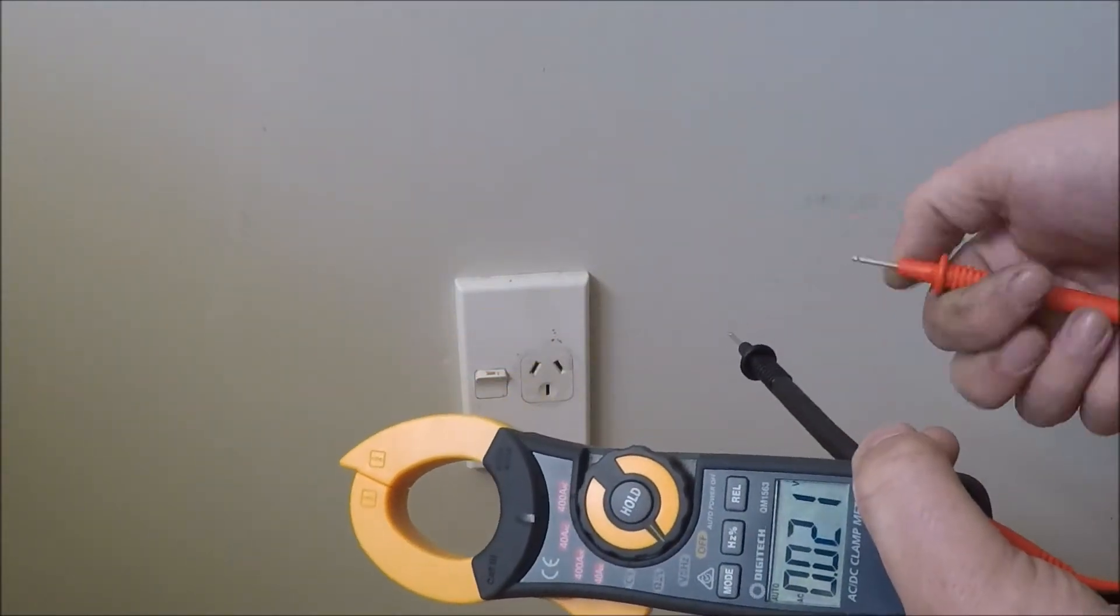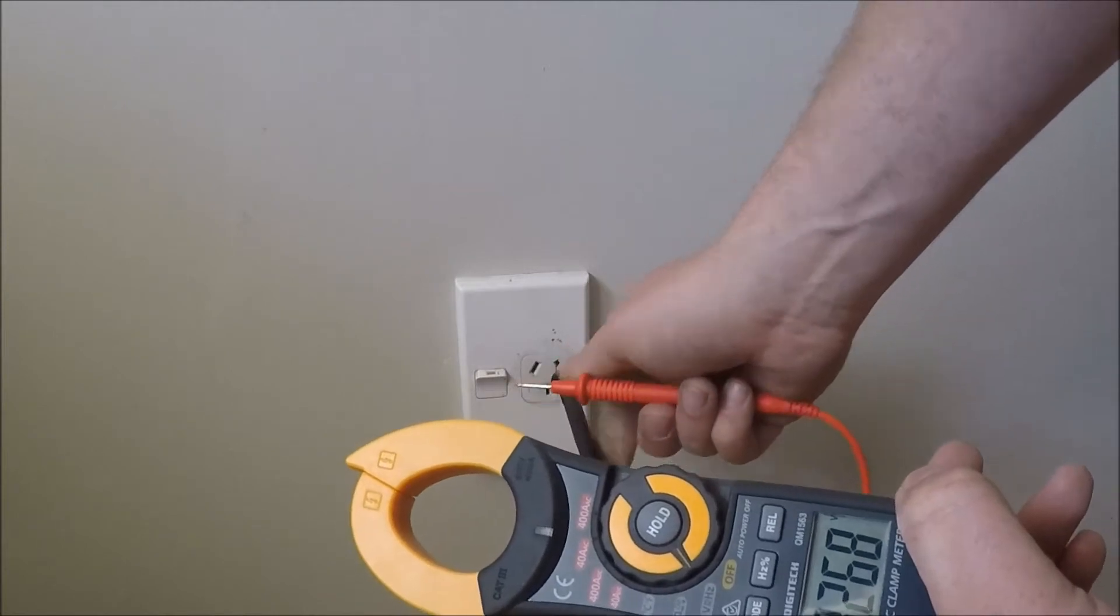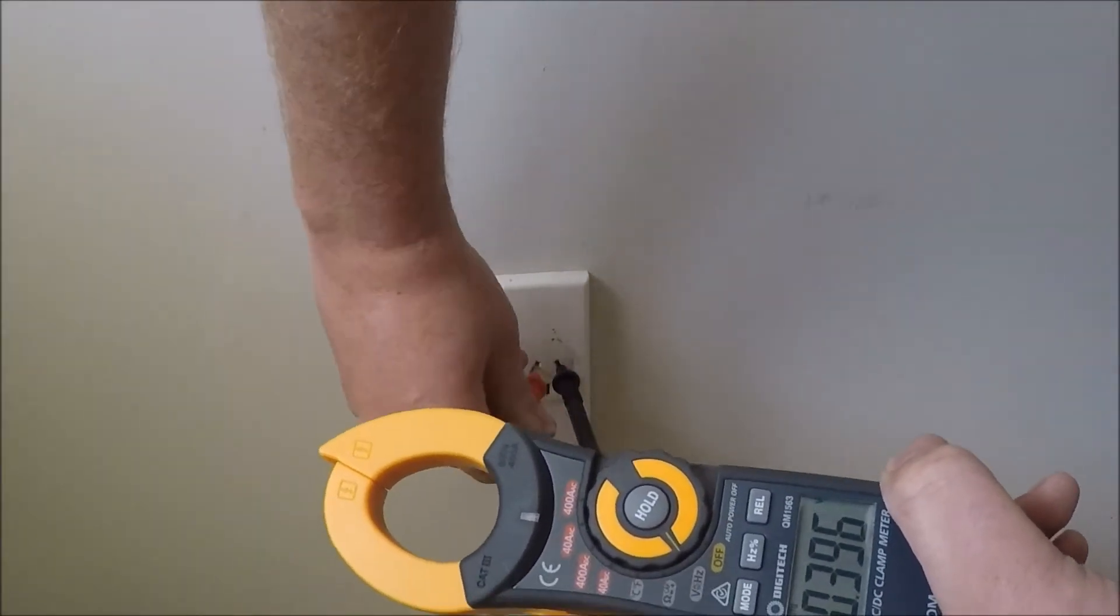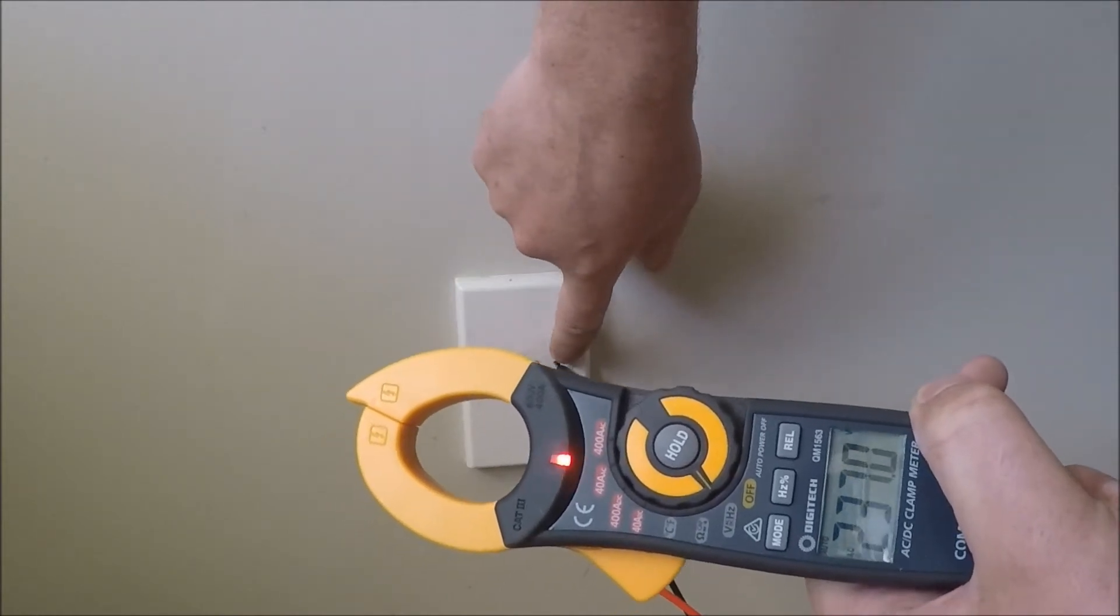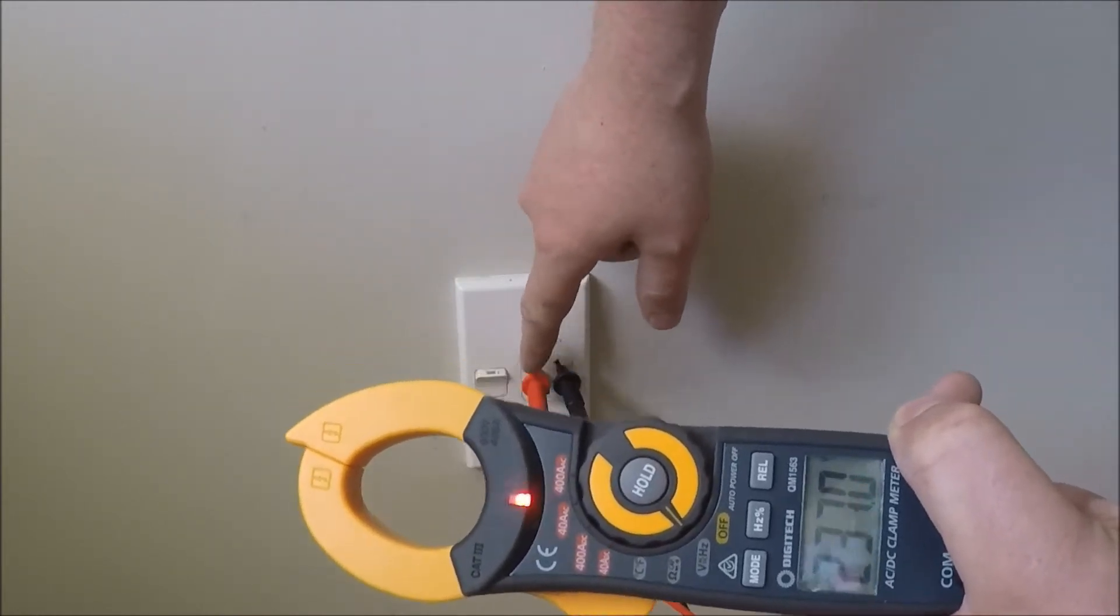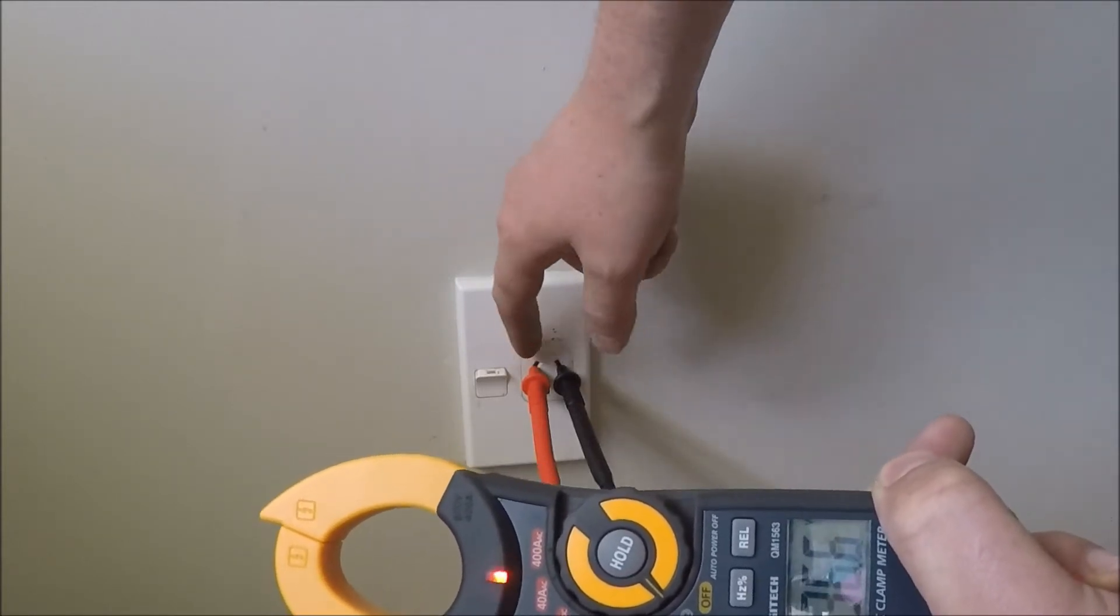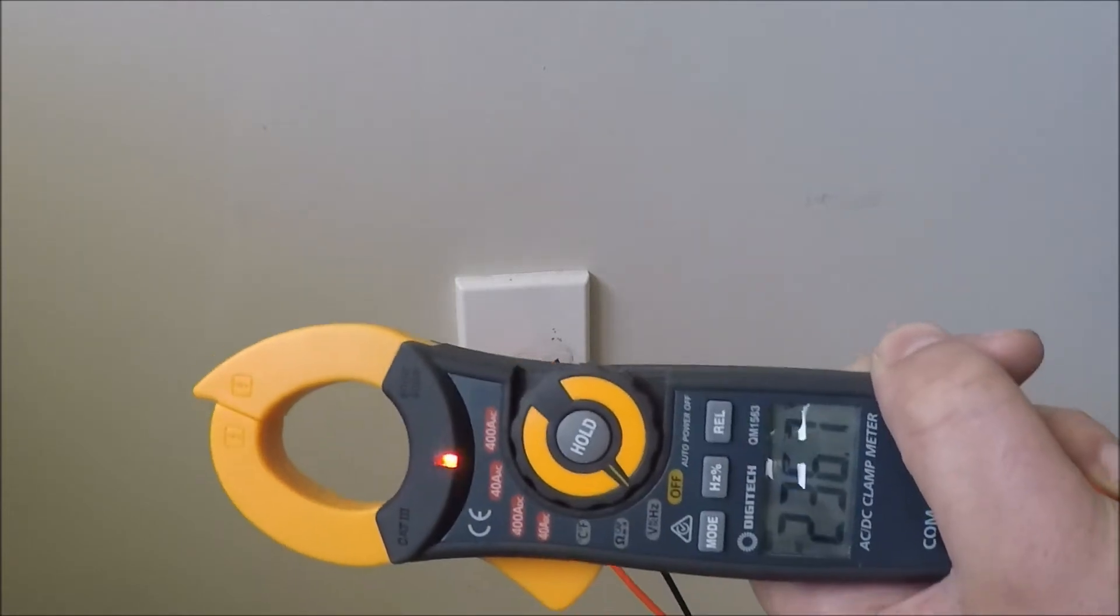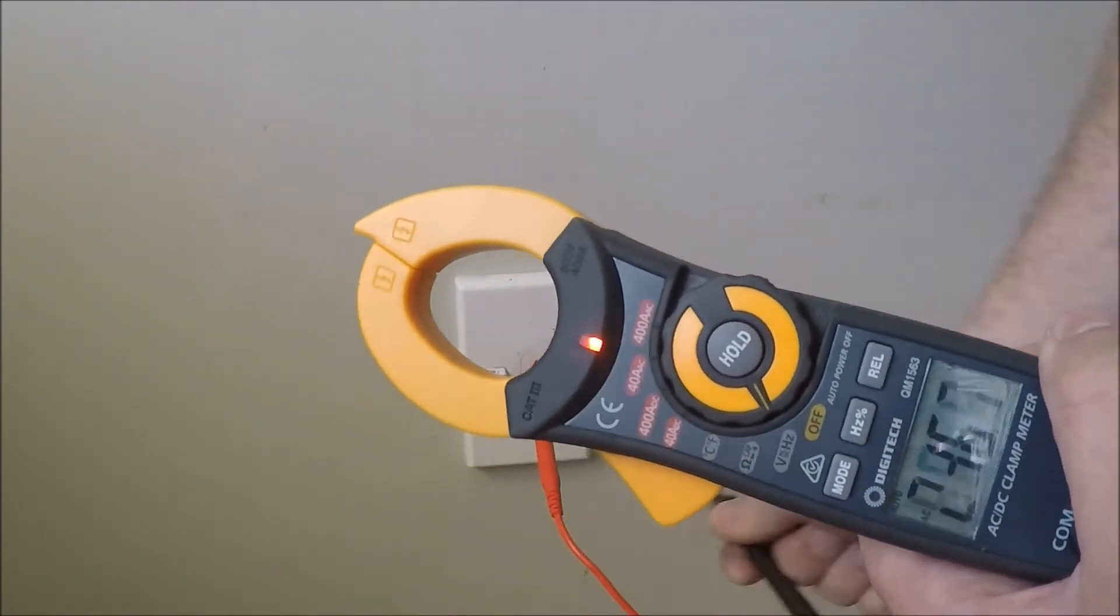And so what I'll do, put one pin in the neutral, and then one pin in the phase, because there is a shutter in the phase terminal here, and you must put something in the neutral first to allow access to the phase terminal. But as you can see my meter is working, it's reading 236 volts.